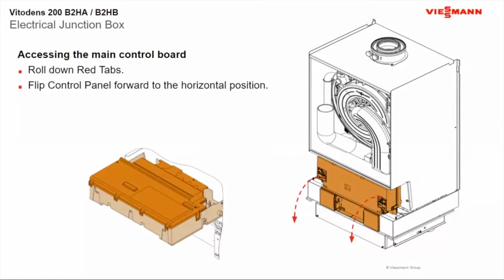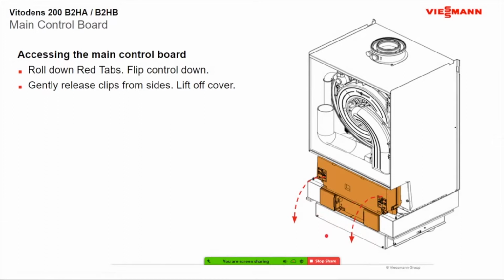The top control holds your interface and where you're going to program everything. There's two little ears on the side, left and right here. They fold down, and then that allows you to fold down the main control. Your interface is normally here in this empty spot. If you don't pull that bottom apron off, it won't allow you to fold that out, but you don't have to pull it out all the way. You can just slide it out a little bit so it allows it to fold down. And that's that little apron at the bottom, if you decided just to look at it and not pull the apron off.